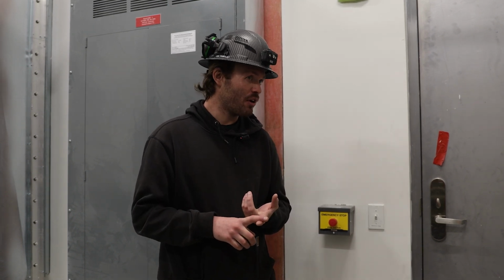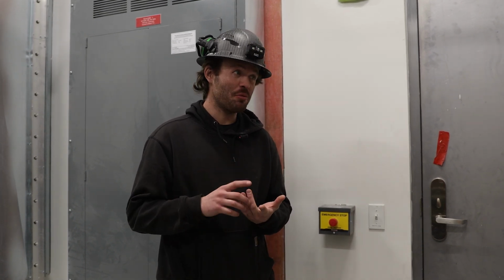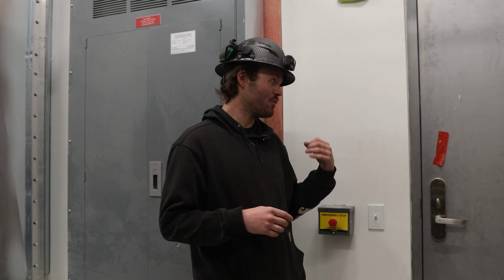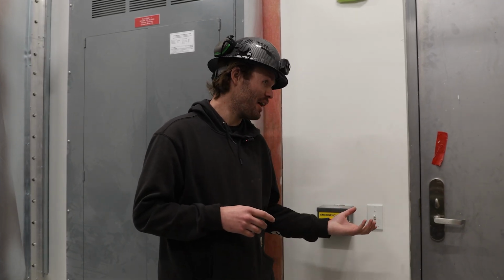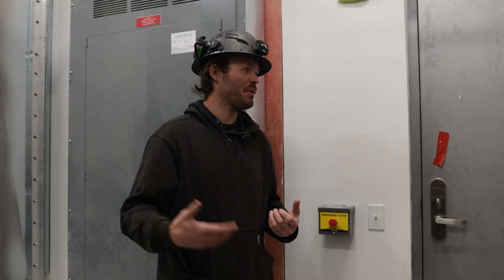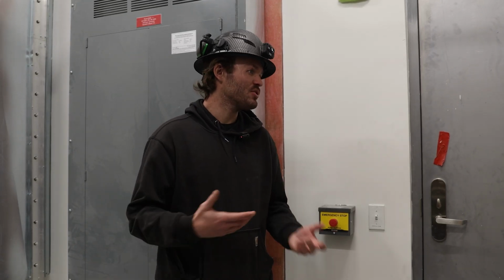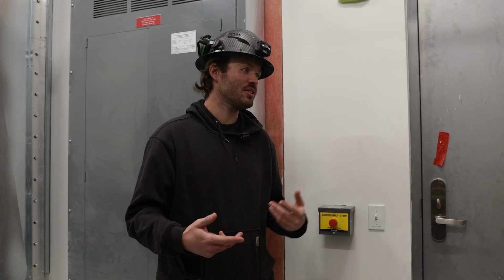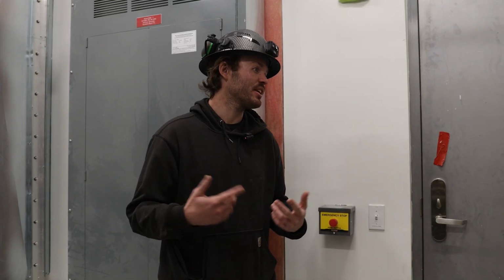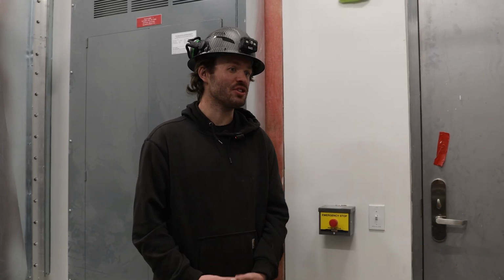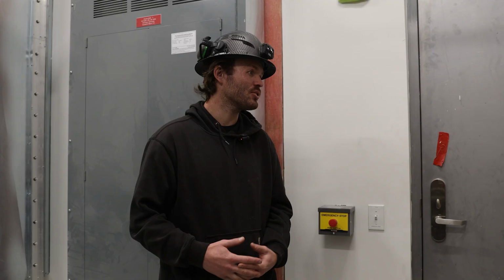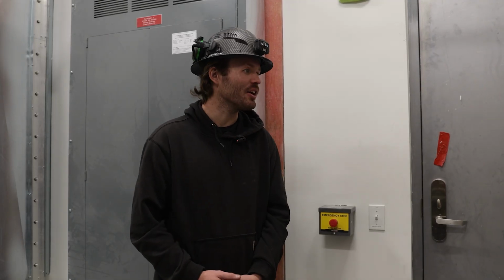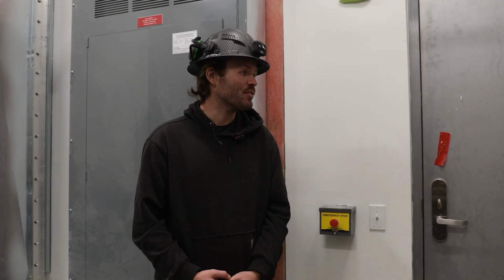You'll get a supervisory signal on the panel for generator run, and that's probably all you're going to get on the panel. So if you choose to bypass your fire alarm panel, that's on yourself, or you can simply do an acknowledge and a panel reset at the very end. So 2 ways to do it. You can bypass the signals or just acknowledge and reset at the end. And when you're finished up, if you're finished before 3 hours, call the alarm company and make sure it gets put back online, because they sometimes forget.